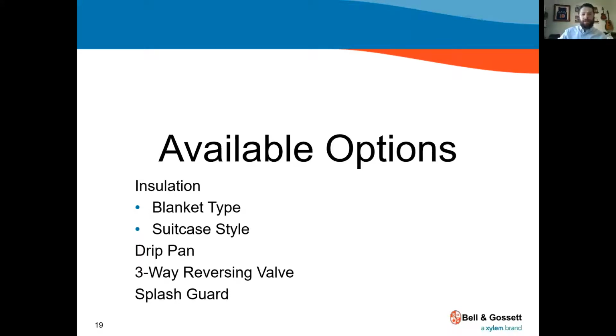Three-way reversing valve is meant to stop blockages. So basically what these do is they reverse the flow of the water temporarily through the nozzles and through some of the plates, so you can clear out any gunk by reversing the water. These are very expensive. And a lot of the scaling things they prevent aren't particularly common in applications that we usually see. So if we're talking plate and frames and we're using generally pretty clean water, I don't know that it's always needed or necessary. So I'd say 90% of the jobs we use, I wouldn't recommend it. But again, if this is an item that somebody's calling for, it's something we can source for you.